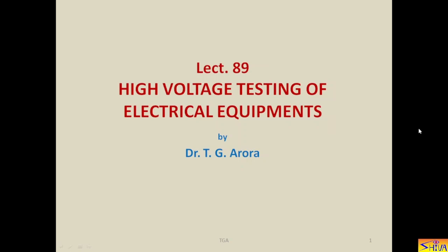I have explained what are non-destructive testings, what is the significance of non-destructive testings, what are the limitations or drawbacks of high voltage testings, then the parameters which define the quality of insulation and the parameter which defines the health of the insulation. I had explained how to measure insulation resistance, capacitance, loss factor, and then how to detect the partial discharges and how to measure the partial discharges.